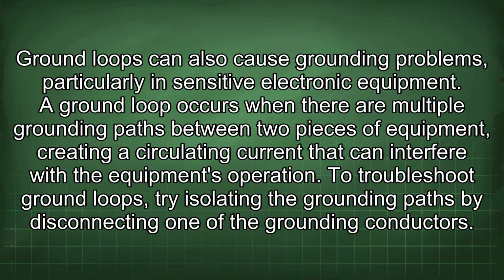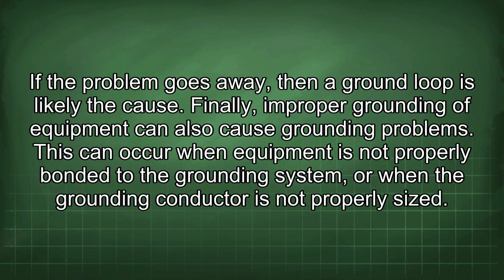Ground loops can also cause grounding problems, particularly in sensitive electronic equipment. A ground loop occurs when there are multiple grounding paths between two pieces of equipment, creating a circulating current that can interfere with the equipment's operation. To troubleshoot ground loops, try isolating the grounding paths by disconnecting one of the grounding conductors. If the problem goes away, then a ground loop is likely the cause.